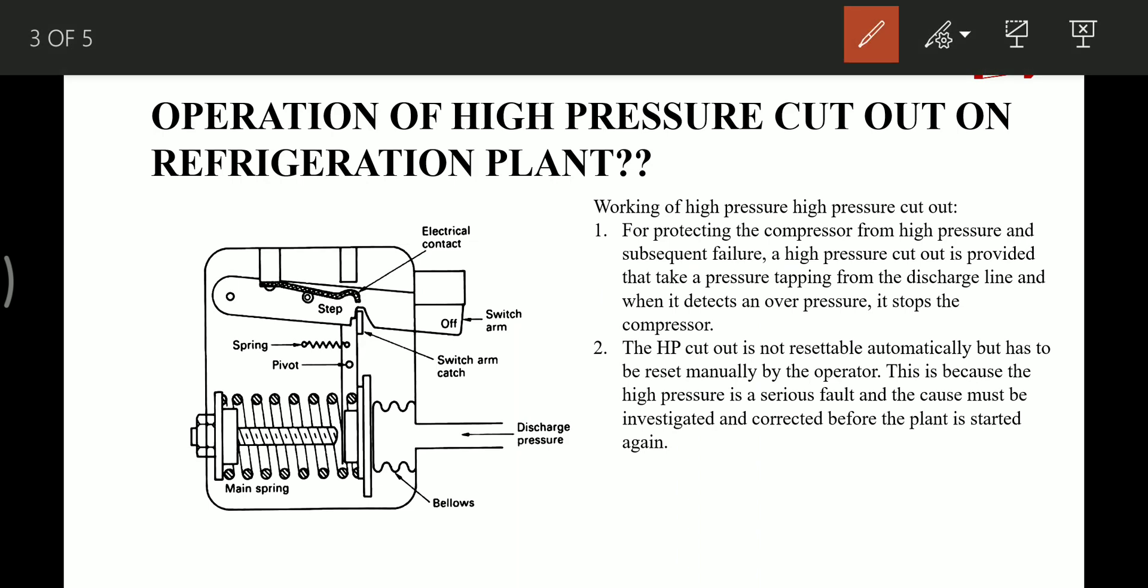How does it work? How does it operate? Before that, let's see the important parts. This is the pipe connecting the discharge pressure side of the compressor. Then this is the bellow in which this discharge pipe is connected. Then this is the main spring. We have this nut which is used to set the pressure of this high pressure cutout. Then we have this arm catch.